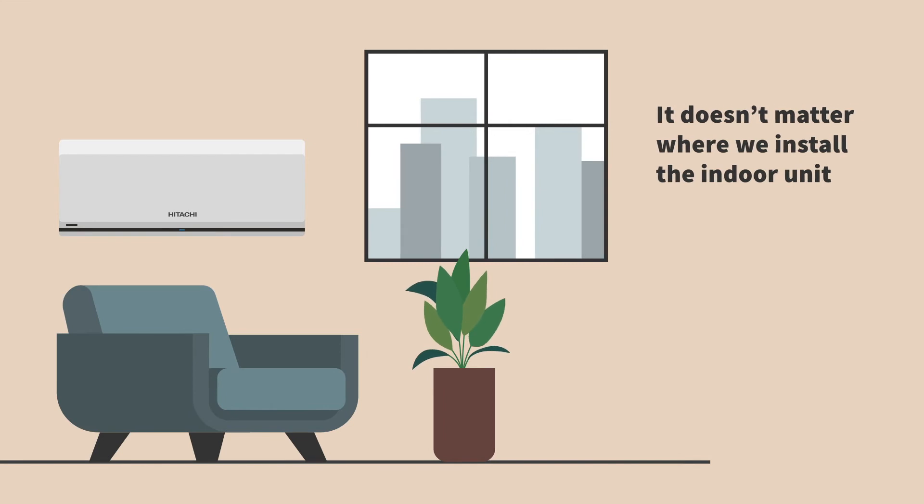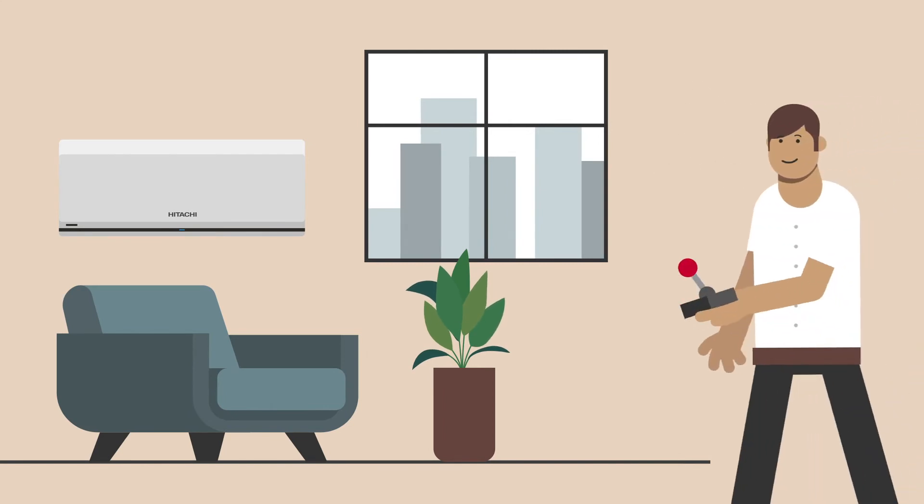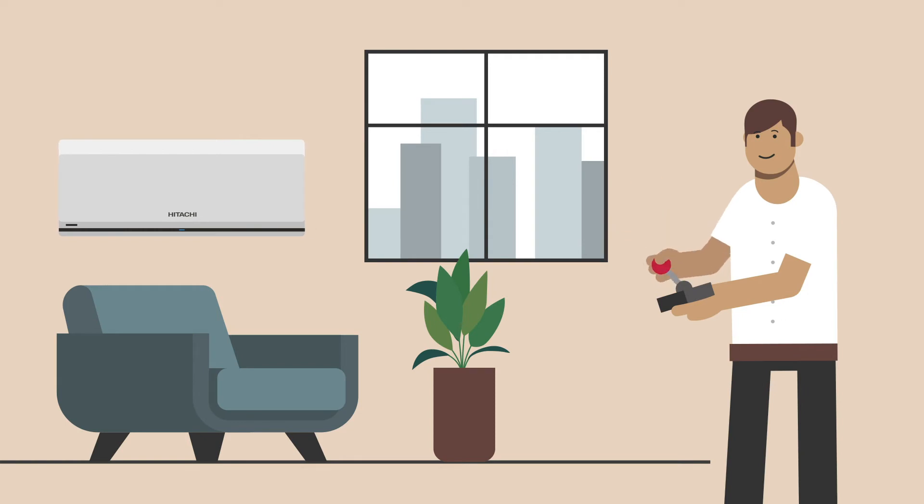It doesn't matter where the indoor unit is installed. It does matter. Install it out of direct sunlight at a suitable height on the wall and where nothing obstructs the airflow. Not doing so can lead to higher household bills.